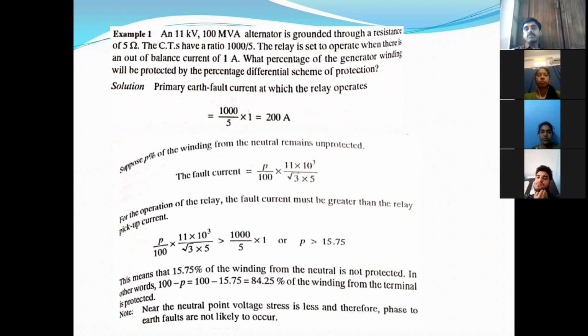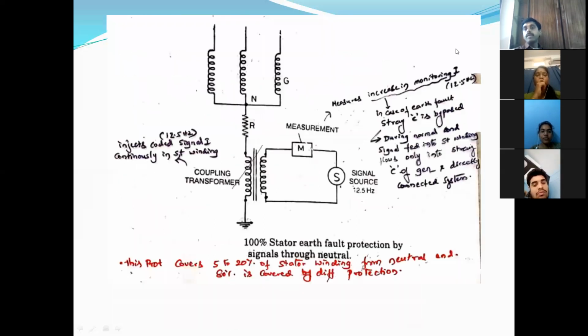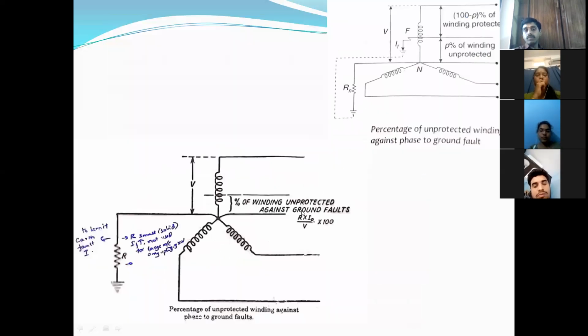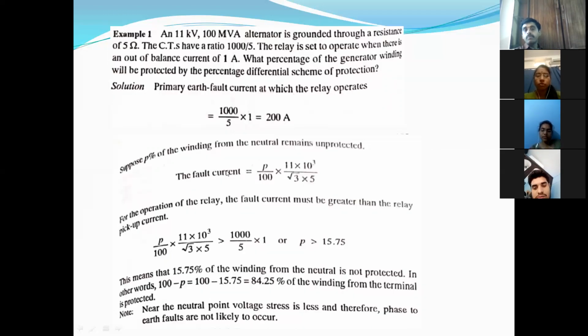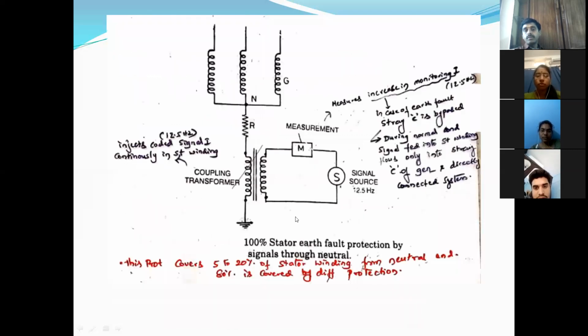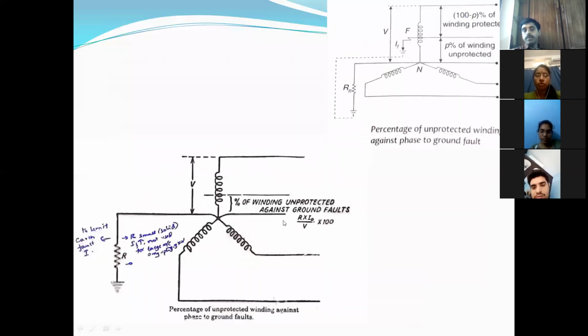What percentage of the generator winding will be protected by the percentage differential scheme? For that, the first step is to calculate, using the formula we have already seen, P, the percentage of the winding unprotected, which is R into I naught by V into 100. From this we can calculate I naught. I naught is equal to P into V divided by R. Can you observe this? P is equal to R into I naught by V, so P into V divided by R is equal to I naught. That is the fault current.